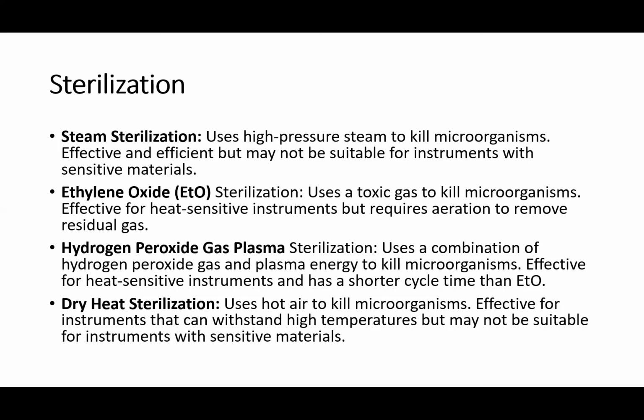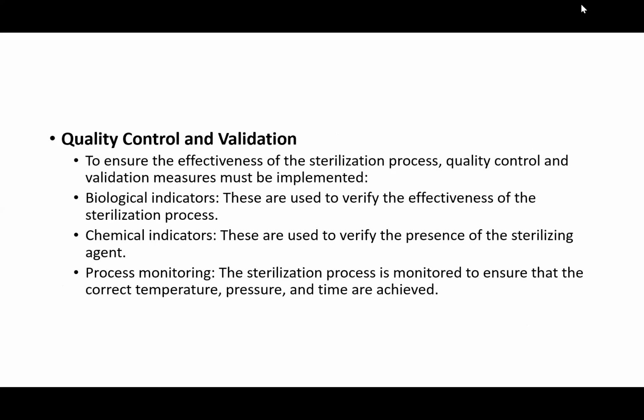You see some of these instruments are left in a hot oven, not autoclave, for some specific duration of time at certain temperature. And sometimes they are even taken directly from the oven to the operation tray. Now, after sterilization, you have to confirm by quality control and validation. You see there are some markers that are placed on these instruments that change color to indicate that the sterilization process has been achieved. So they are indicators for quality control and validation.